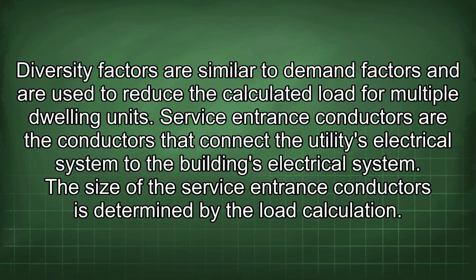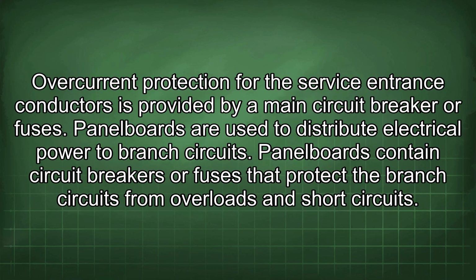Service entrance conductors are the conductors that connect the utility's electrical system to the building's electrical system. The size of the service entrance conductors is determined by the load calculation. Overcurrent protection for the service entrance conductors is provided by a main circuit breaker or fuses.